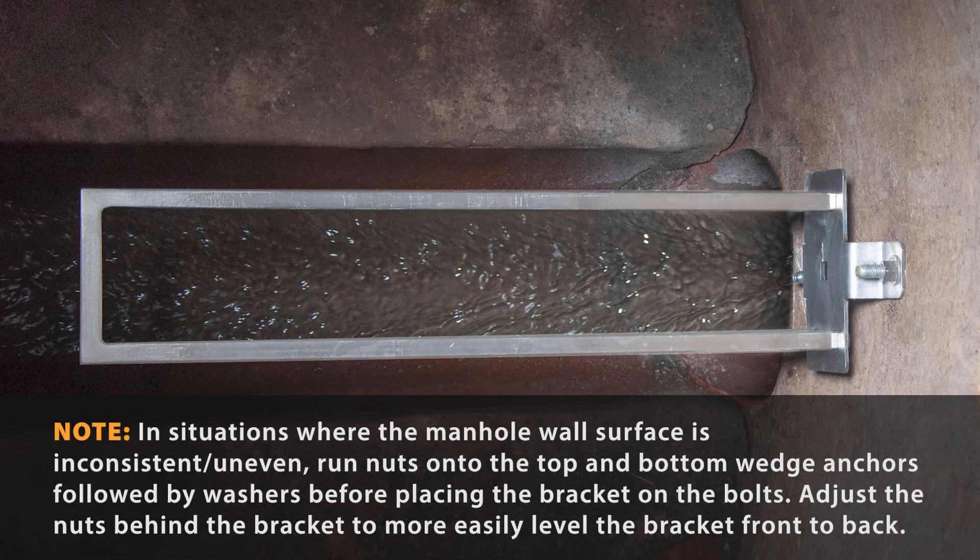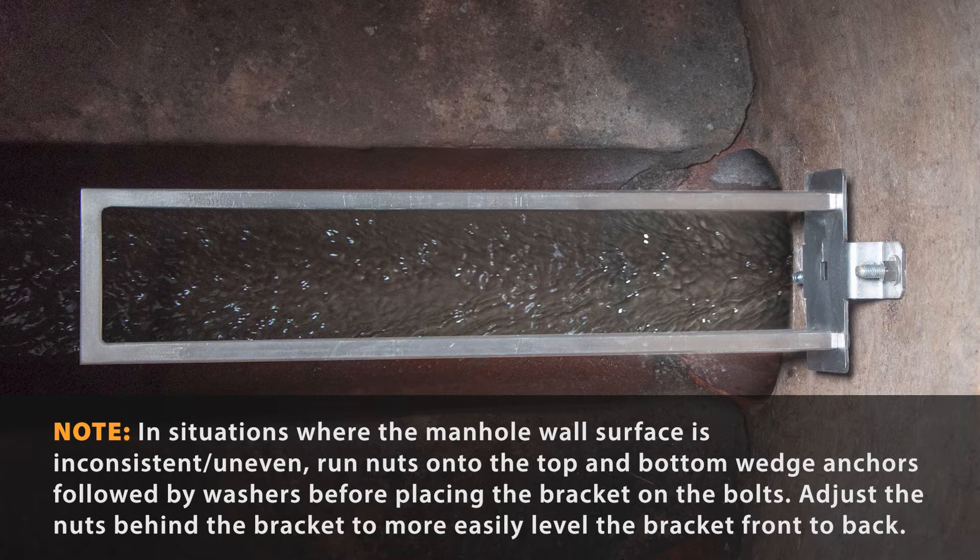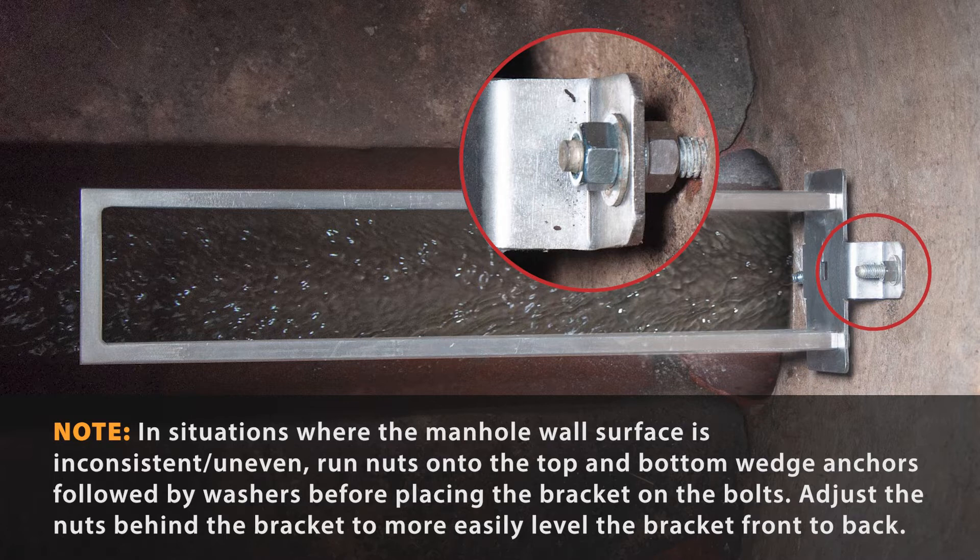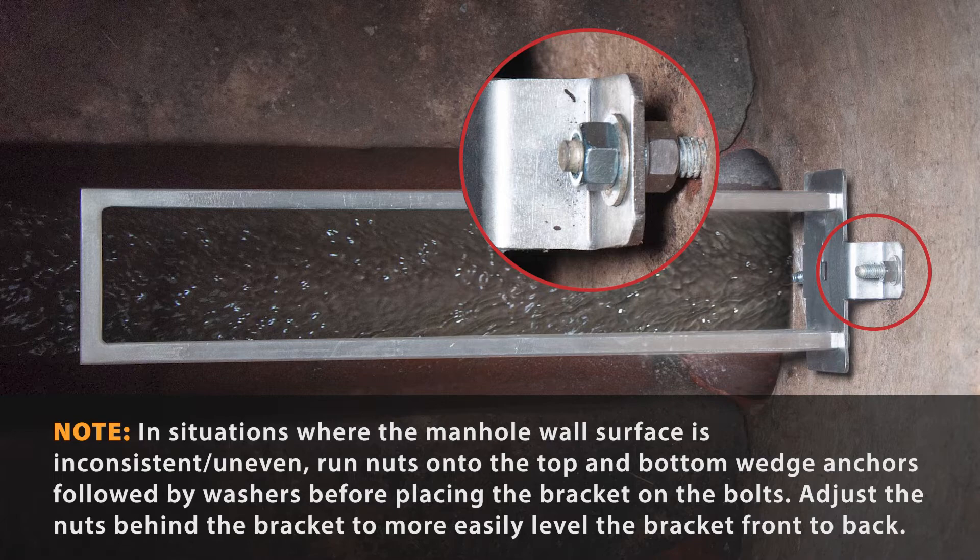In situations where the manhole wall surface is inconsistent or uneven, run nuts onto the top and bottom wedge anchors, followed by washers before placing the bracket on the bolts. Adjust the nuts behind the bracket to more easily level the bracket front to back.